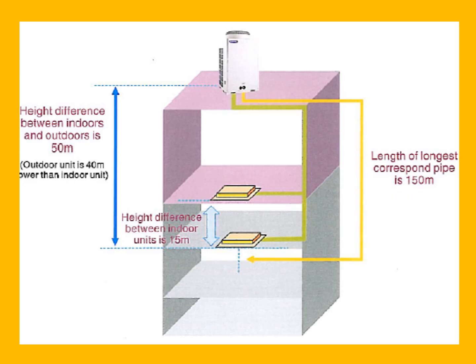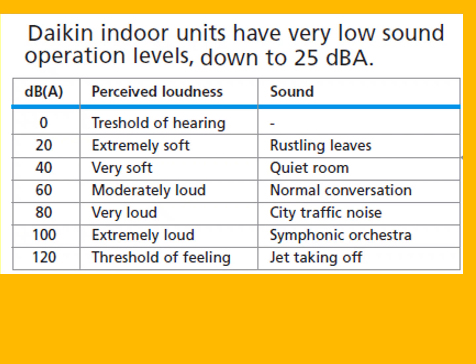Friends, this particular table shows the height difference between indoor and outdoor unit, which may be maximum 50 meters, and also the length of the longest piping is 150 meters. So these two figures, 50 and 150, are to be remembered while using a VRF type system. Friends, Daikin type indoor units have very low sound operation level down to 25 dBA. If you want to understand what this level of 25 dBA is, you can see it is between the noise of rustling leaves and a quiet room.